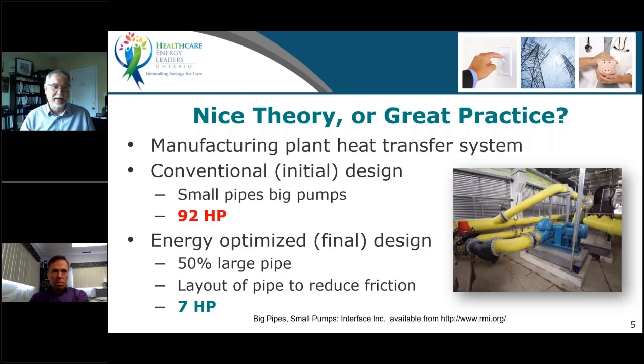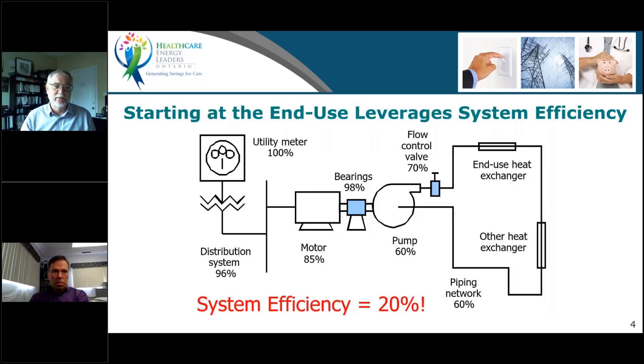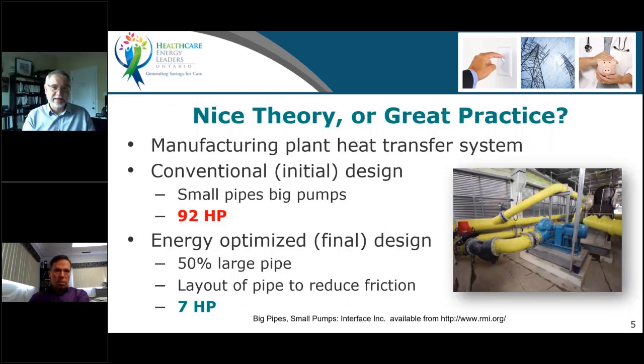So you might have been thinking, well, Steve, this is nice theory, because people have said that before, but is it great practice? Nice in theory, but can you put it into practice? So those nice swept elbows, right, things like that, larger pipe. Now, granted, the larger pipe is going to cost more, better piping practice is going to cost more. But when you think about the fact that the cost of energy in one of these systems is 20 to 30 times as much as the cost of the initial system, it might just make sense to do it. If you want to read more about that one, there's an article at RockyMountainInstitute.org called Big Pipes, Small Pumps, because the practice years ago was small pipes, big pumps when energy was cheap. So the idea here is we need to dig down in the driven system. And that's kind of the approach we're going to take moving forward.